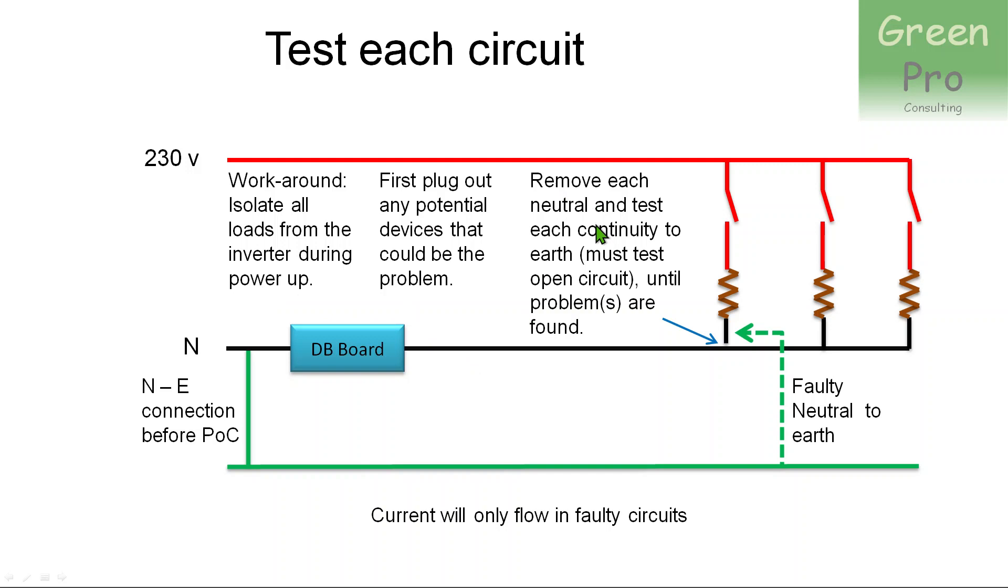Okay, if it's not one of those two, then you have to get a guy in that starts scratching in your DB board. And what you do is you remove each neutral circuit, so you keep the circuit off, and then you start testing for continuity between neutral and earth in that circuit. And if it's not, then you connect it back onto the neutral and you go through everything until you hopefully find the problem.